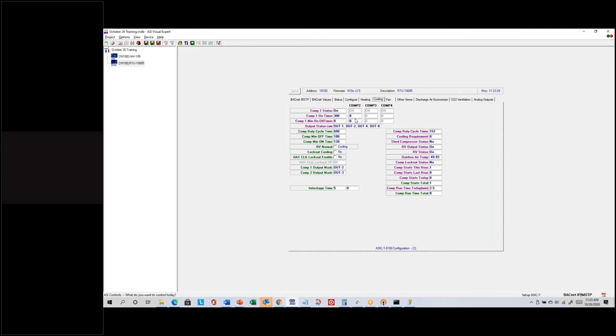We're at 25 percent, so the first compressor wants to be on for half the base time. We'll wait until the calculation goes past 50 and then see compressor two turn on for some fraction of the base time. The same duty cycle time and minimum on/off times are shared by both compressors. We always lead with one — there's no lead-lag. There's no feature to indicate compressor one is larger or smaller compared to compressor two.